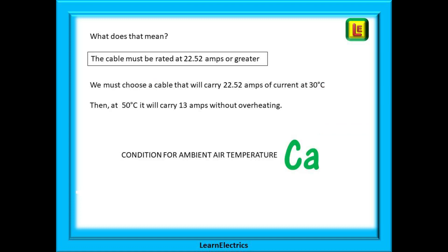We should choose a cable that will take at least 22.5 amps. What does this mean? We must choose a cable that will carry 22.52 amps of current at 30 degrees centigrade since 30 degrees is our reference temperature. The table then tells us that a cable that can carry 22.52 amps at 30 degrees will be able to carry 13 amps at 50 degrees without overheating.